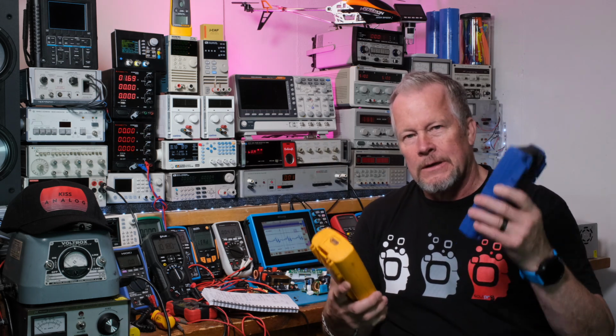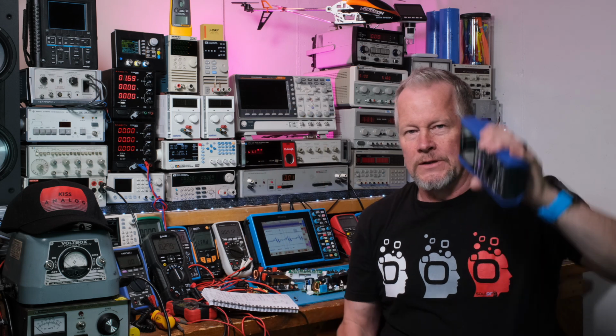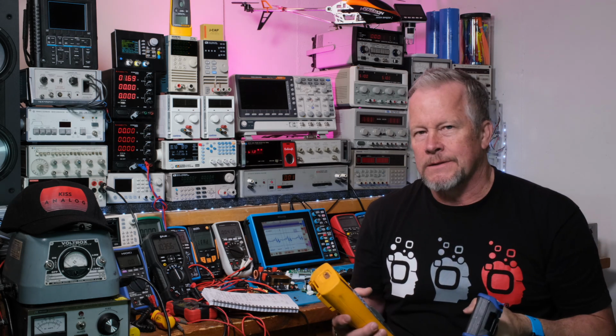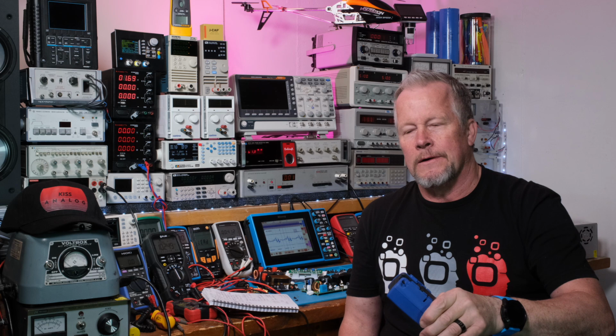So if this was a Keysight 1282A, it would have an IP rating of 67. The 6 is the highest number you get in the dust particulate rating. The other one was 4, so this is 2 numbers higher. That means it's dust proof, essentially dust proof, okay? The 7 means it's kind of waterproof. What it means is, I think, it's 3 feet of water.